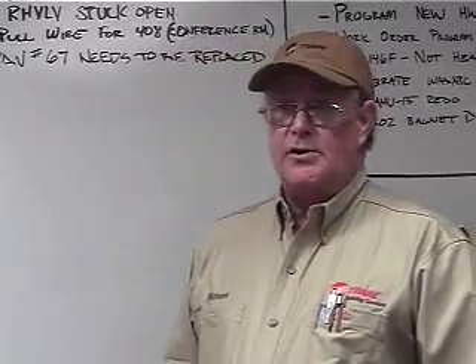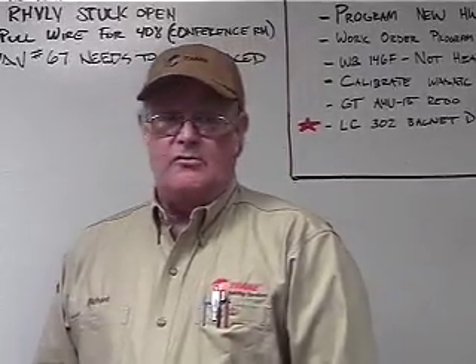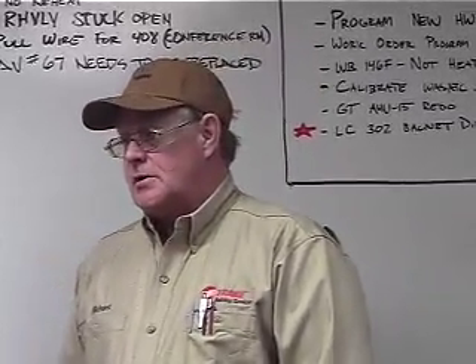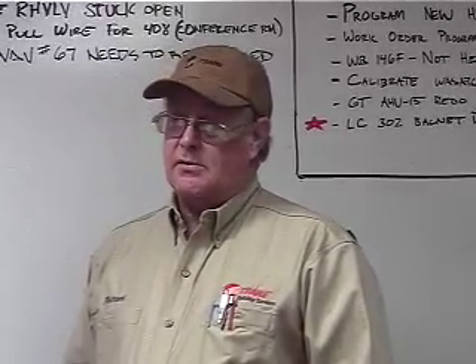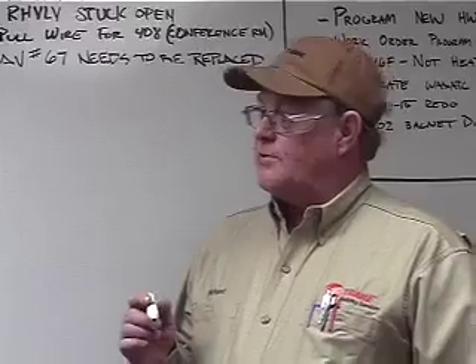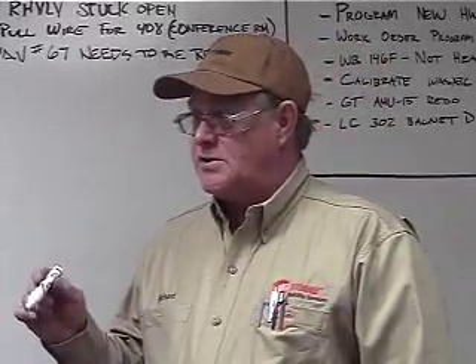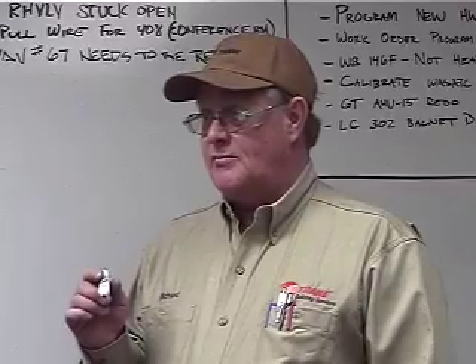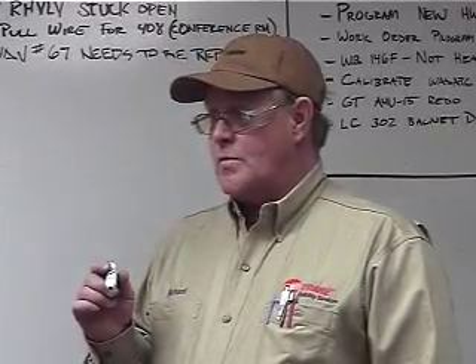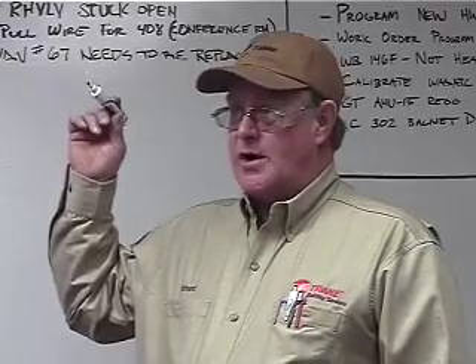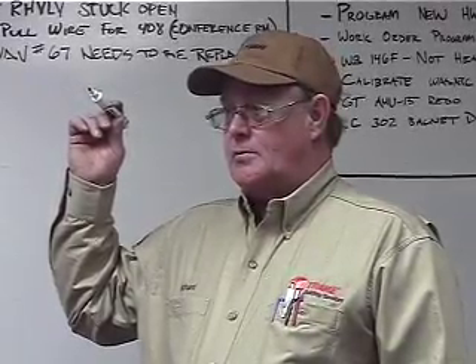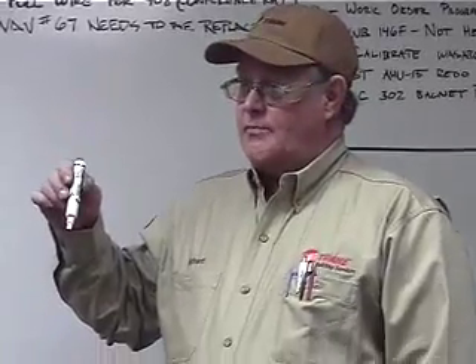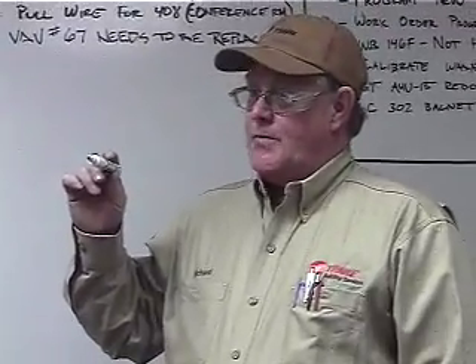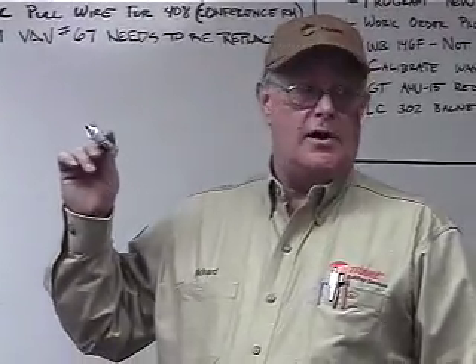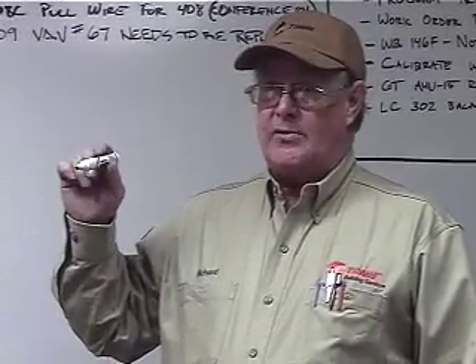This chiller over here is running on 460 volts versus your other two chillers from Trane that are on 4160. Can you tell me the difference or the reason why we've got 4160 versus 460 volts? What happens if you have a high voltage? What happens to your amp draw? It goes down. A 460 volt chiller will have a higher amp draw than a 4160 would have.